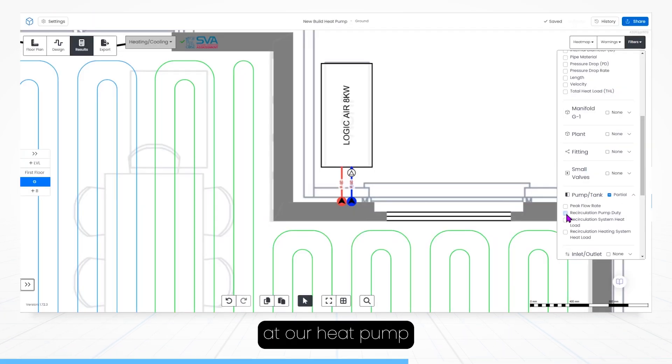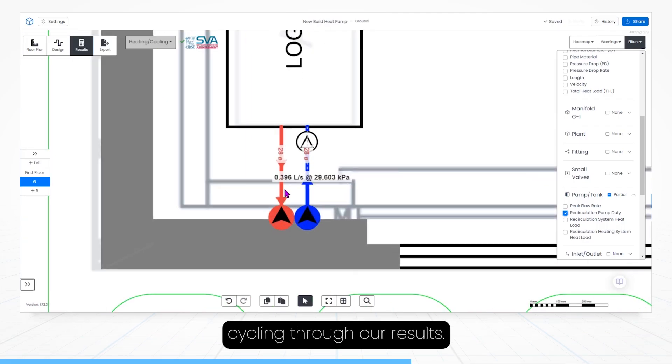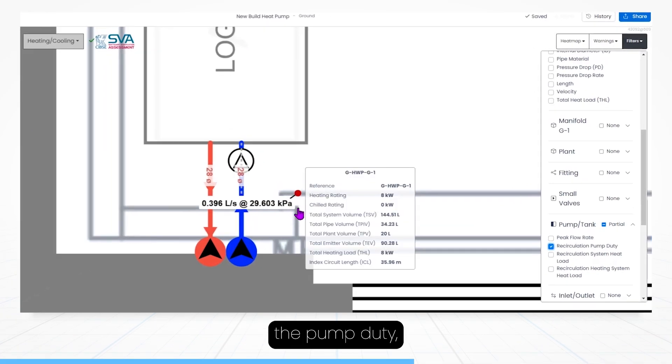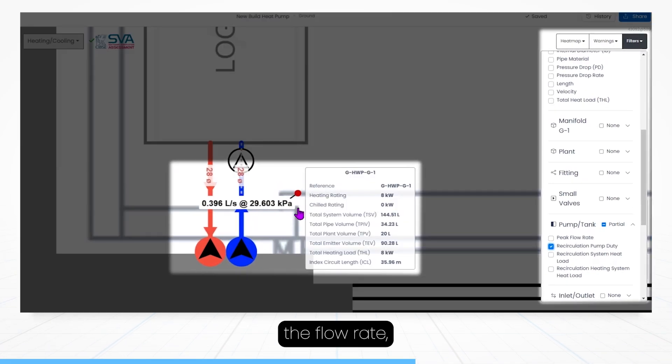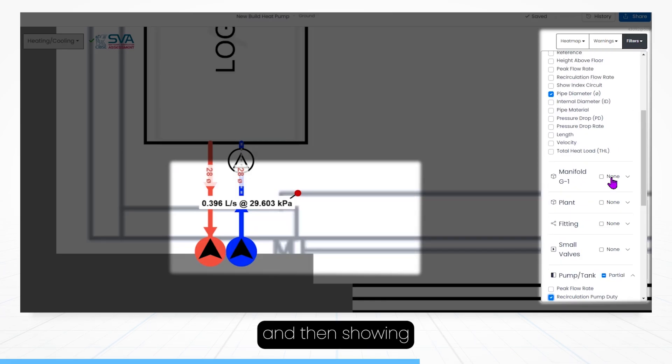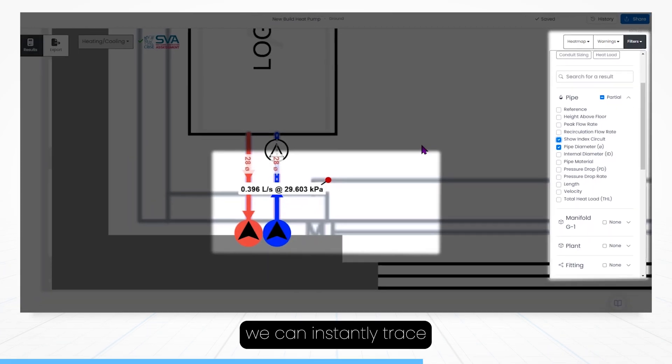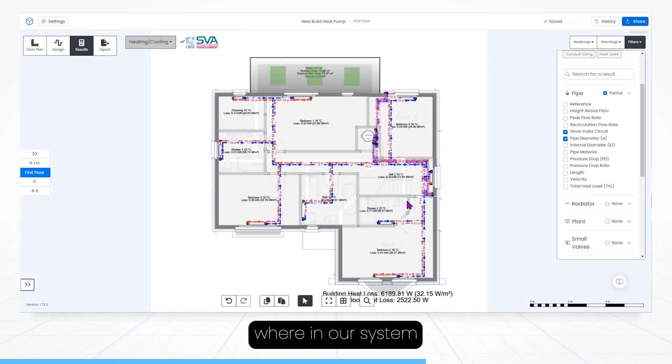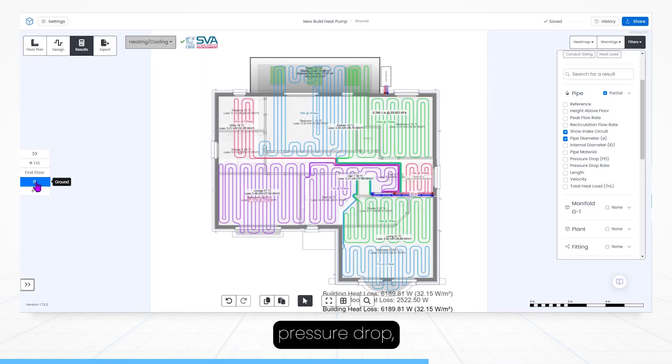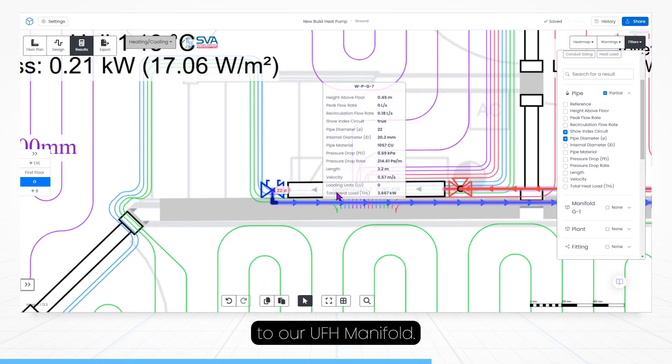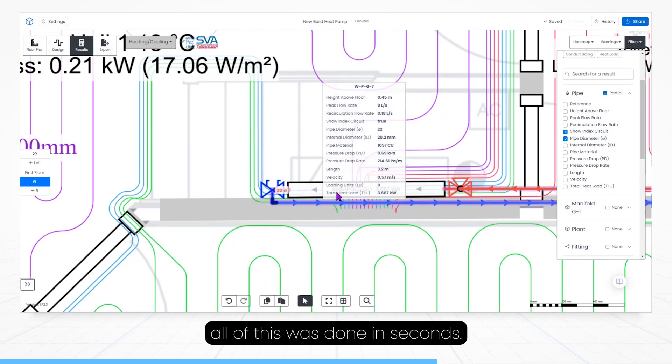Now let's take a look at our heat pump. Cycling through our results, we can already see the pump duty, the flow rate, and the pressure drop. And then showing the index circuit, we can instantly trace where in our system we will see the most significant pressure drop, which is the piping to our underfloor heating manifold. Might I remind you, all of this was done in seconds.